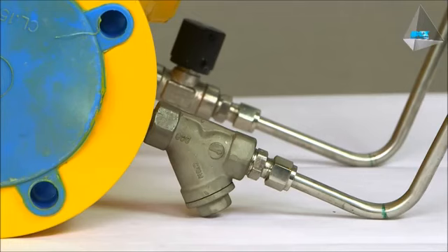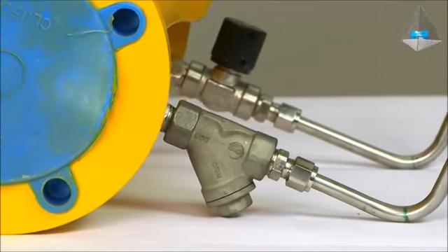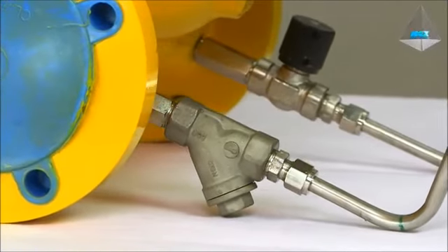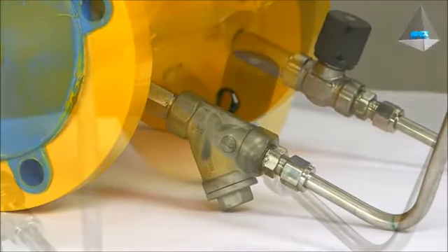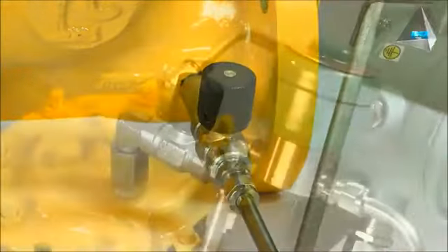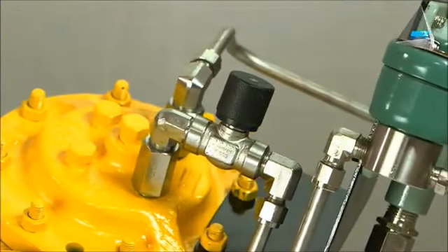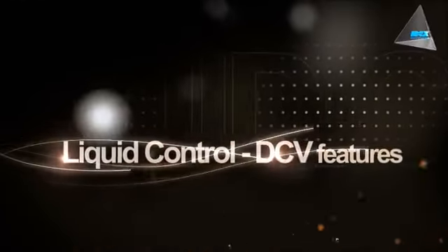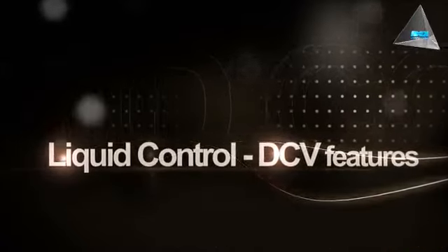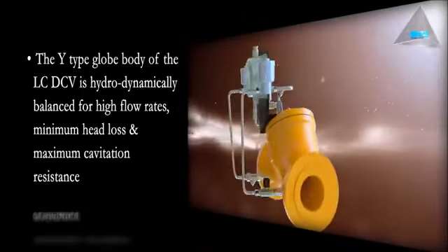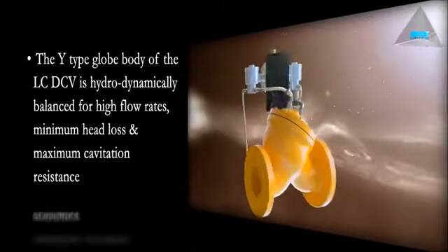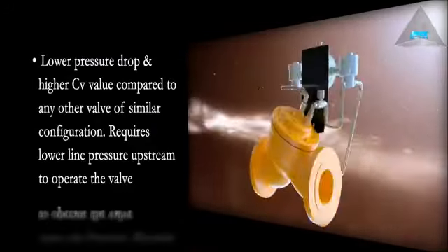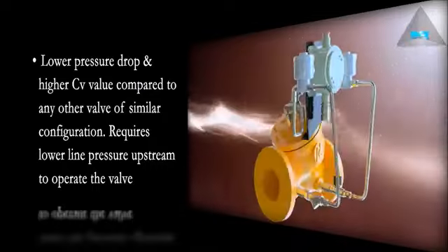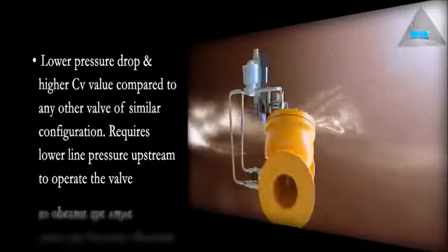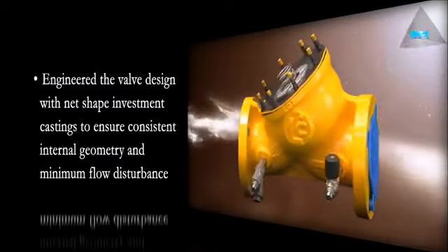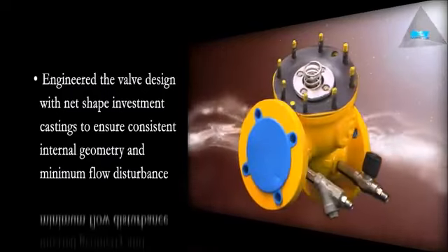A Y-type strainer is provided at the inlet side of the tubing to filter the solid dust and particles, preventing them from entering the diaphragm chamber. Needle valves are provided for fine-tuning the flow rate. The basic valve can be configured with an infinite number of control possibilities while still maintaining a simple, robust construction with simple servicing if ever required and few parts that may ever need to be replaced.